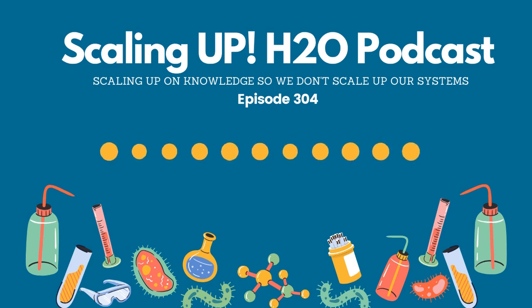Now, let's say it's been 60 days or 30 days or whatever, however many days you want to leave the corrosion coupons in the system, and now it's time to take them out. And I didn't mention this before, but when you handle a corrosion coupon, you want to make sure you're gloved. Just the small amount of oils that are on your fingers will change how that corrosion coupon will interface with that water. And I can't tell you how many corrosion coupons I've received from water treaters in my lab where I can see your perfect thumbprint on there. Well, folks, that's not a good exposure to the water on the entire corrosion coupon surface. So those aren't good coupons. And the reason that those happen is because they did not glove themselves and those oils transferred from their thumb to the corrosion coupon.